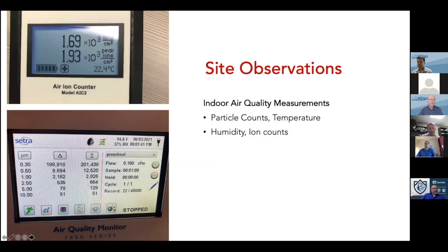So we spent the extra money and got an air quality meter that actually measures to 0.3 microns, and you can see the counts. Now this is in a preschool classroom, and you can see that those counts are extremely high. Part of it is the outside air counts were extremely high the week we were there. And also if the units aren't running, or if the units are running and there's a lot of bypass, that'll drive those counts up as well. So we've got good baseline numbers saying these counts are probably 4 times higher than they should be. And that's what we're trying to find a solution for: how do we get these particle counts in the 0.3 to 1 micron range about 4 or 5 times lower than what they are showing right now? So that's a challenge.